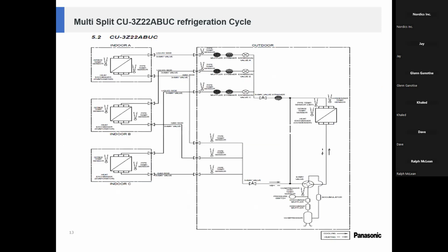And that's your three-zone refrigerant diagram. As you can see, hot gas, high pressure discharge vapor is going to leave the compressor going into your condenser if you're doing cooling, and if you're doing heating, it will go to your indoor unit through your four-way valve, and we are bringing back 100% vapor back to the compressor, and then the cycle repeats. Okay.